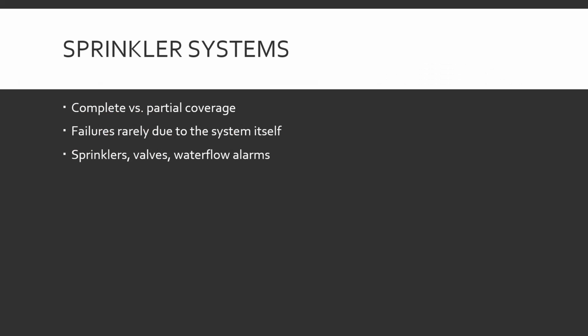Sprinkler systems. Complete versus partial coverage. Self-explanatory. Either the whole building is protected by sprinklers, or only certain high danger areas are protected by sprinklers. Failure is rarely due to the system itself. It's true. The sprinkler system itself is fairly simple. Water goes in, or not, we'll get there. But the system is designed so it's got to be set off in order to fail. It just doesn't fail for no reason.